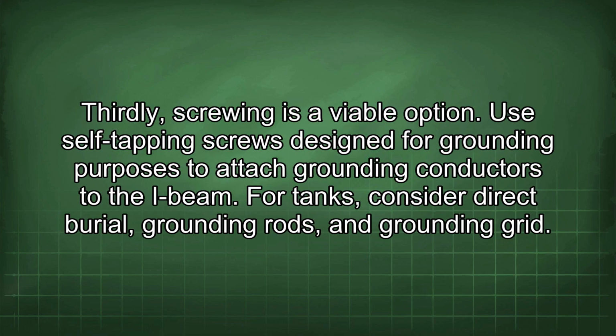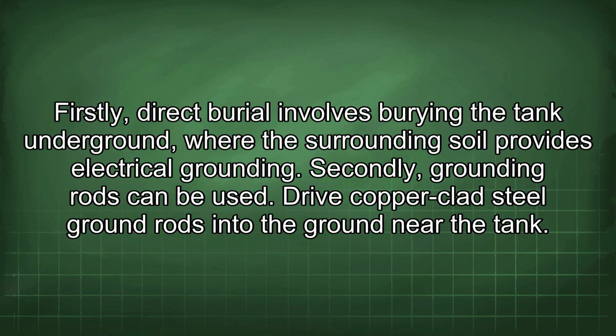Weld grounding studs or plates to the I-beam, ensuring a good electrical connection. Thirdly, screwing is a viable option. Use self-tapping screws designed for grounding purposes to attach grounding conductors to the I-beam. For tanks, consider direct burial, grounding rods, and a grounding grid. Firstly, direct burial involves burying the tank underground, where the surrounding soil provides electrical grounding.